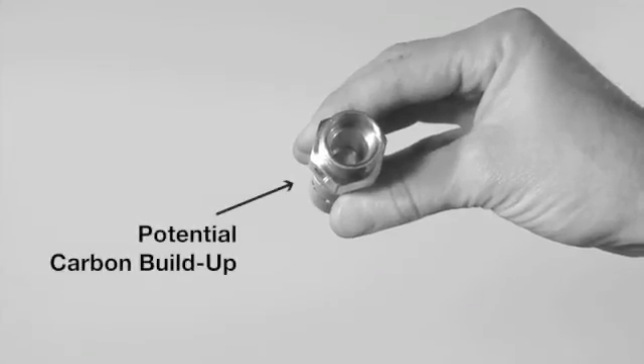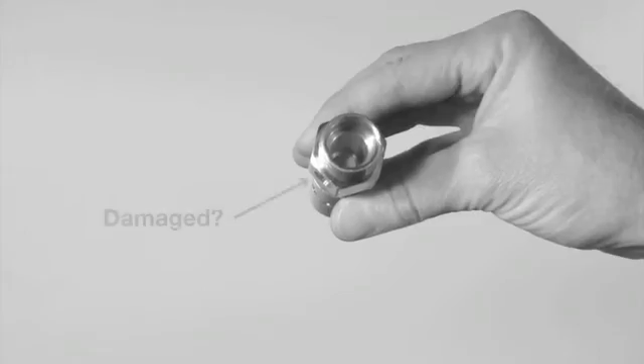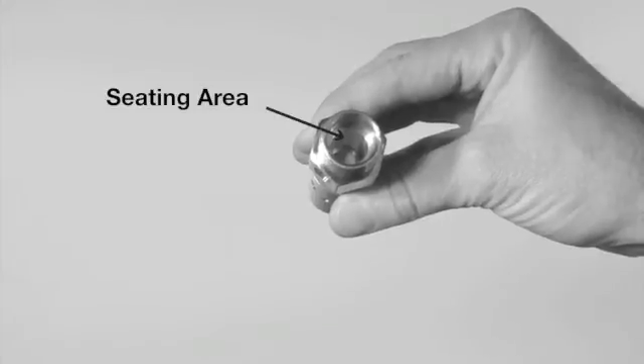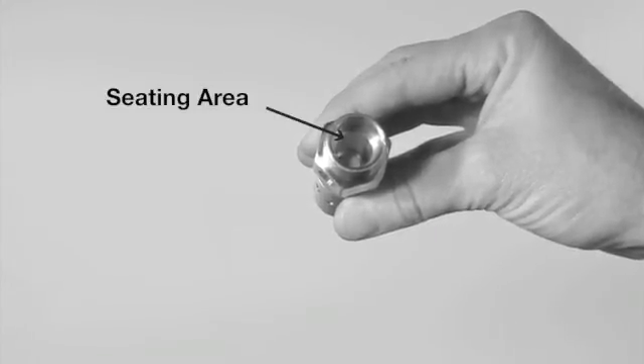If the valve appears only to be dirty with carbon buildup, washing it with a mild soap may be sufficient. If any part appears damaged, or the seating area where the disc seats inside the valve body appears pitted, replace the valve assembly entirely.